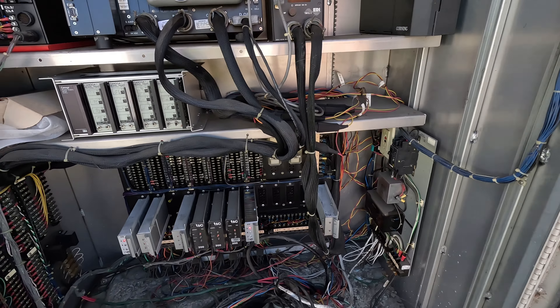We had a tag reader — actually it was kind of funny — on one of those intersections down there on the coast, Bayview. It was a license plate reader, and I just went to cutting everything that wasn't the new cable we pulled out. It blew a hole in my client's setup. I was like, 'What's down there?' It was a two-conductor — they used an old loop cable to hook up a tag reader and just hooked up a constant power to it. You got to undo all this. This cabinet's getting junked — we're throwing this thing away, or going back to the city.